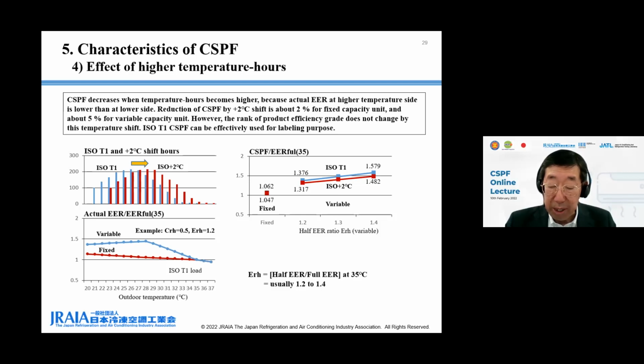Reduction of CSPF by plus 2 degrees shift is about 2% for fixed capacity unit and about 5% for variable capacity unit. However, the rank of product efficiency grade does not change by this temperature shift. ISO T1 CSPF can be effectively used for labeling purpose. Next, please.